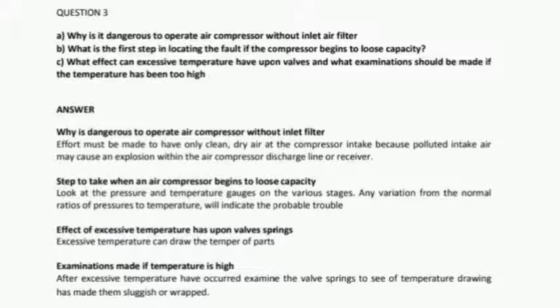Sluggish valve action and leaking valves can also cause a reduction in the capacity of the air compressor. So if this is detected, the valve should be overhauled.